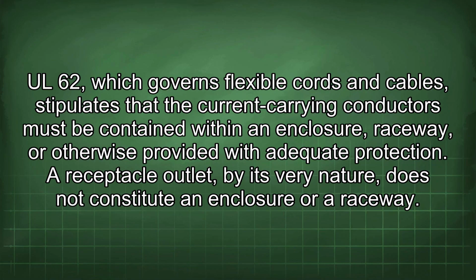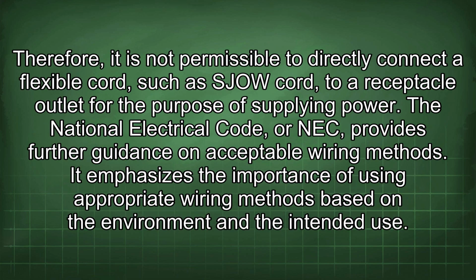UL 62, which governs flexible cords and cables, stipulates that the current carrying conductors must be contained within an enclosure, raceway, or otherwise provided with adequate protection. A receptacle outlet, by its very nature, does not constitute an enclosure or a raceway. Therefore, it is not permissible to directly connect a flexible cord, such as SJOW cord, to a receptacle outlet for the purpose of supplying power.